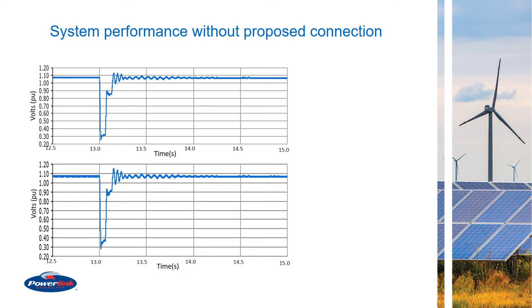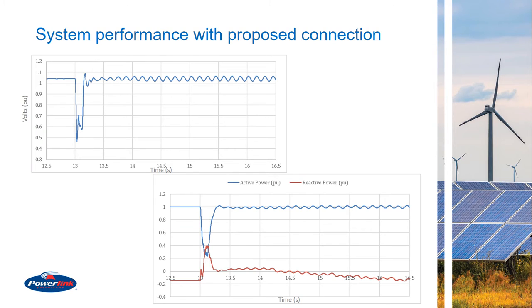For the FIA analysis, it is important to make sure that system performance is satisfactory without the plant under consideration for FIA, so that the adverse impact due to the new connection can be identified clearly. These figures show the system response without including the plant under consideration for the FIA. Figures show that system performance is satisfactory without the new IBR. Now, what we see here is the system response after the new plant under consideration was connected to the rest of the network. A series of contingencies in different parts of the network were run to assess the impact of the new IBR. What we can see here is that a fault was applied, and when the fault is removed, the system does recover from the fault.